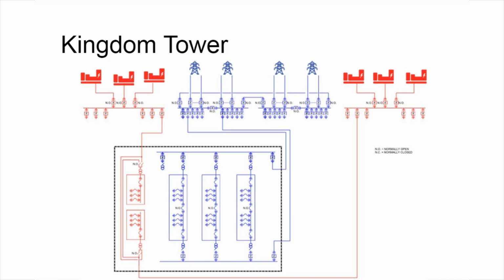But you can see we brought in multiple utility sources to the site. Each of the utility sources is tied together with a normally open, normally closed switch configuration. So that's all the blue wire. That then distributes throughout the building and hits unit substations that are double-ended, so that one feed comes from a different utility source than the other, and then multiple sources throughout the building. We do the same thing with the emergency power system.